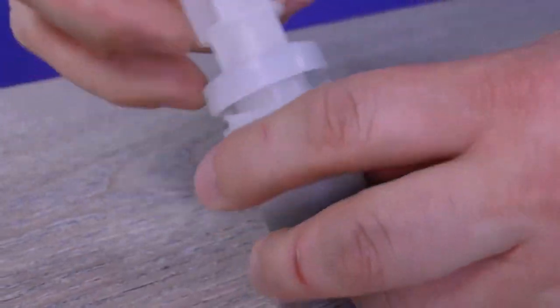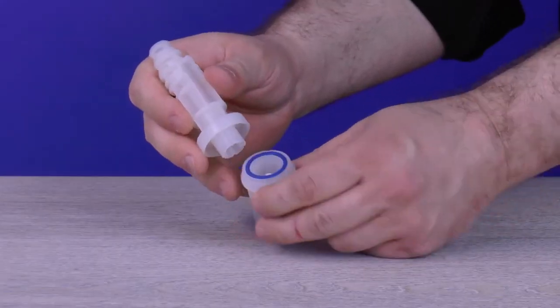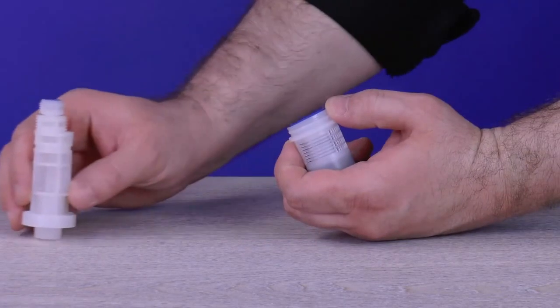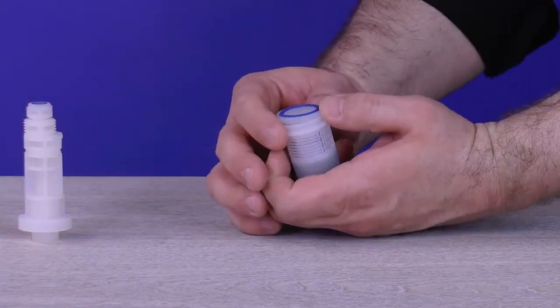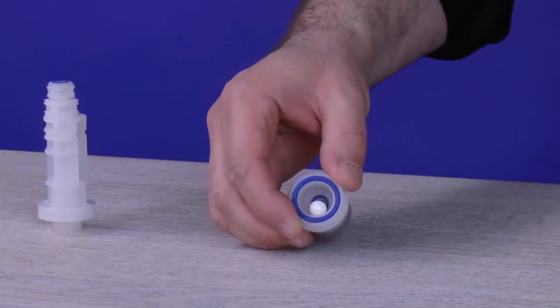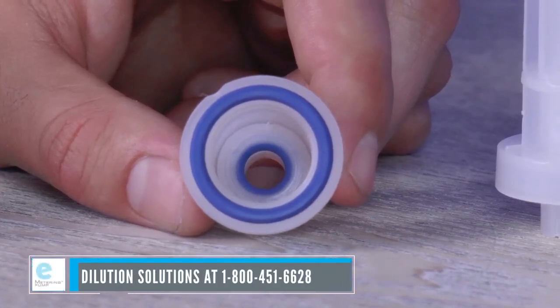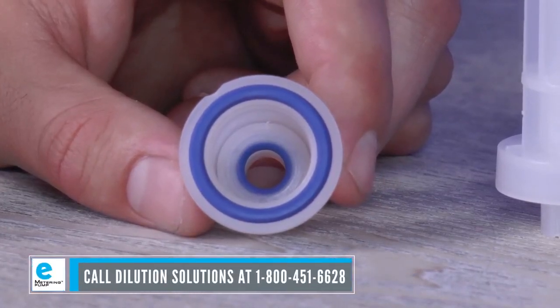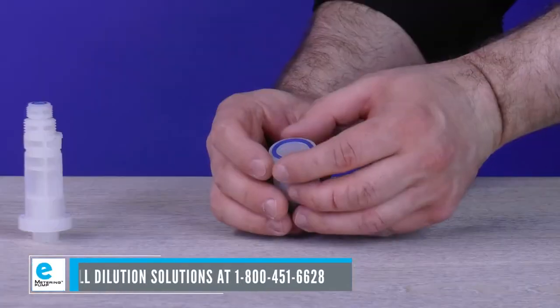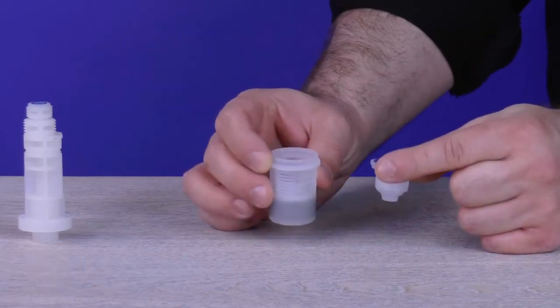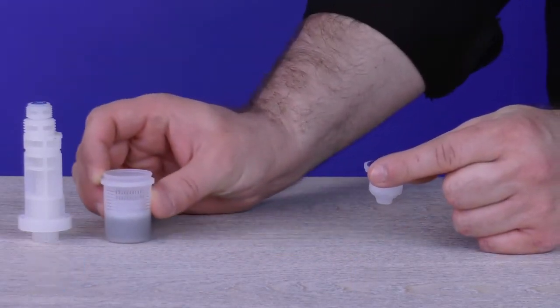The filter seat may stick to the filter body. Make sure it rests in the filter basket instead to avoid losing the ceramic ball. Set the filter body aside and locate the ceramic ball in the filter seat. If there is no ceramic ball, call Dilution Solutions at 1-800-451-6628 for assistance. Pull the filter seat out of the filter basket and set the filter basket aside.